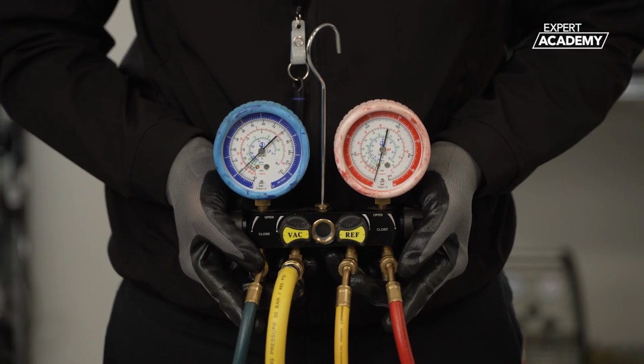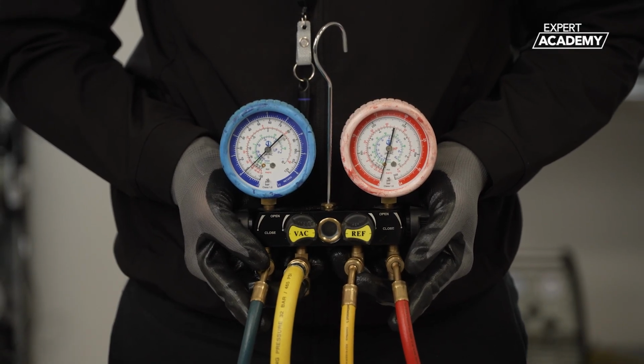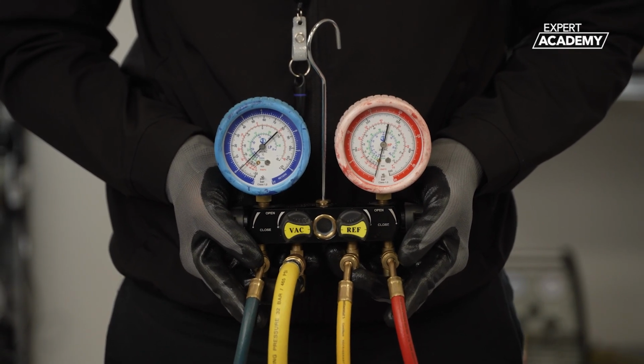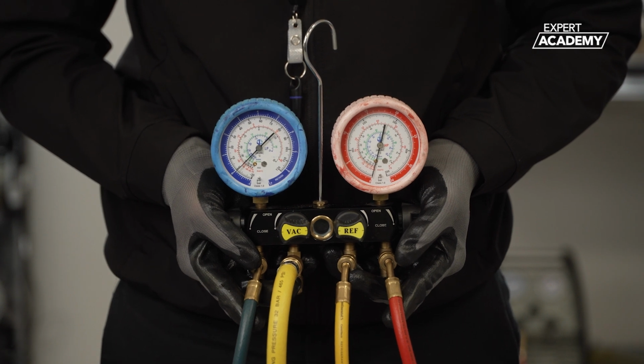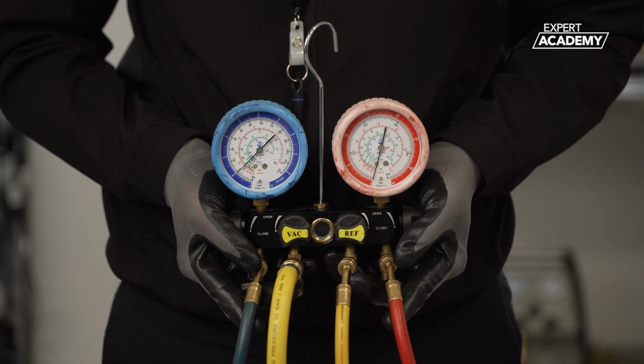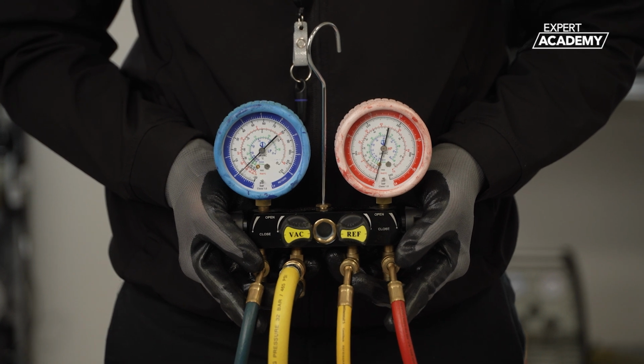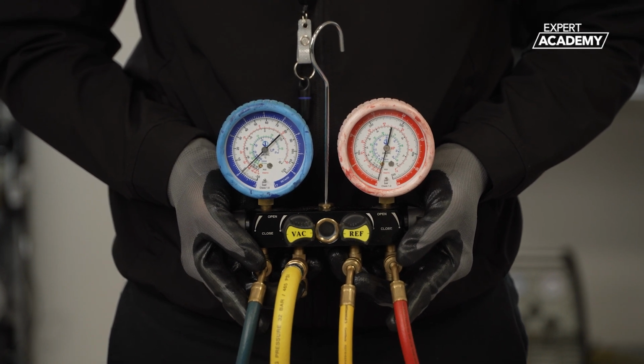A manifold gauge is used to check the pressure of refrigerant systems. It is essential for diagnosing whether the system is correctly charged. They also serve checks such as adding refrigerant and detecting refrigerant leaks. These gauges are available in both analog and digital versions.